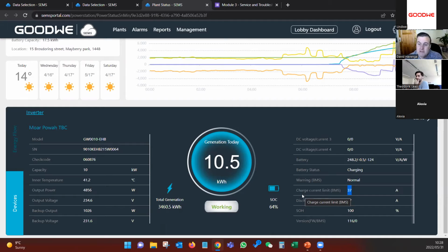So you can always double check to see that your charge and discharge current limit is correct, because as we know, our maximum charge and discharge power is always going to be the voltage times the current, which gives our maximum charge or discharge power. And then lastly, the state of health of the battery and the inverter firmware version. Normally the last two digits is ARM firmware, and the digits ahead of that is DSP. Just a bit of information, it's not vital for you to remember.